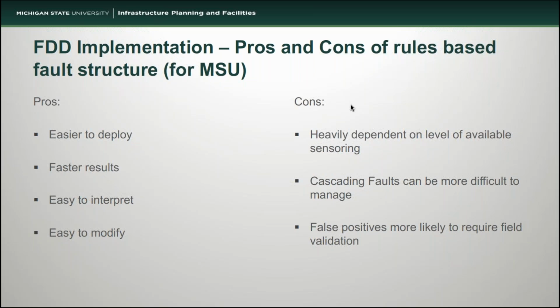Now you can put data checks in place to say, well, if the chiller is not running and the air temperature is above or below a certain point, we don't want this fault to trigger. But the more checks that you put in place, the more likely you are to mask a real problem if you have a communication issue or if something's commanded on that's not actually running. It's a slippery slope when you start to try and manage those cascading faults. And then false positives really require field validation in the majority of instances. Slide.